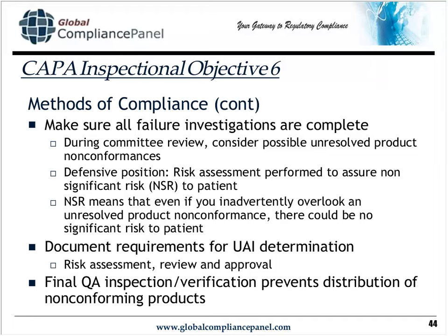When you conclude that you have NSR, non-significant risk, what you're saying is that even if you inadvertently overlook an unresolved product nonconformance, as you can see two bullet points up, there's still going to be no risk to the patient because you've looked at the reported failure investigation and its conclusion, and you've determined whether there is a significant risk to the patient.